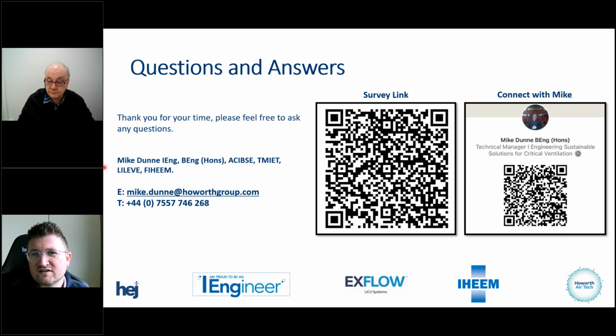Yeah, so another thing that I didn't mention within the presentation is fire strategy. So when we do the validation, we take a look at the fire strategy, we look at the fire commissioning documents for the SFDs, for the smoke fire dampers. Various trusts look at this differently, and again, the scope and the specification is written by the authorising engineer for vent around fire strategy. We literally just make note of it within our reports, and we don't do a full in-depth detail assessment of the smoke fire damper strategy because it's not massively our experience really.